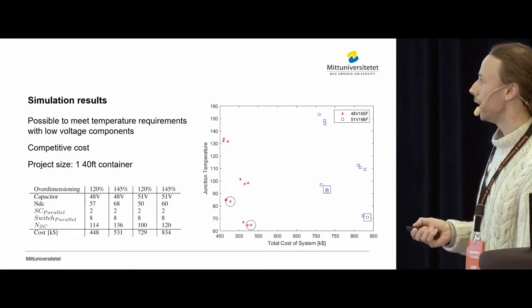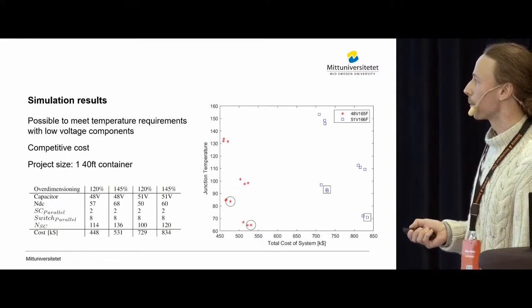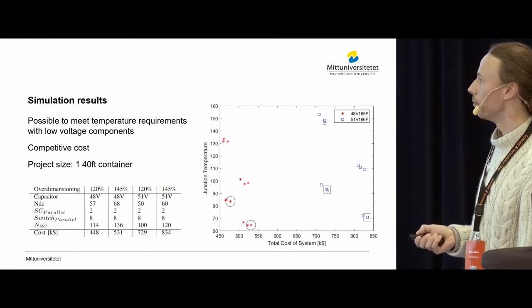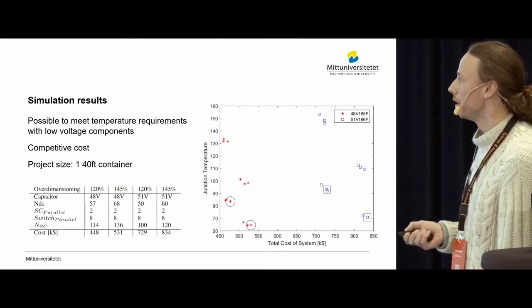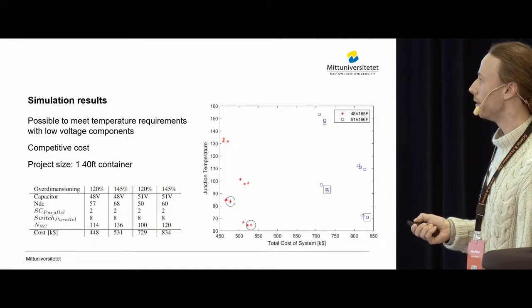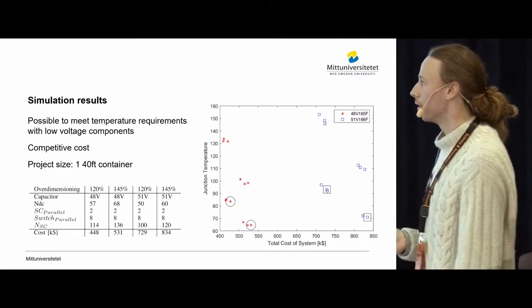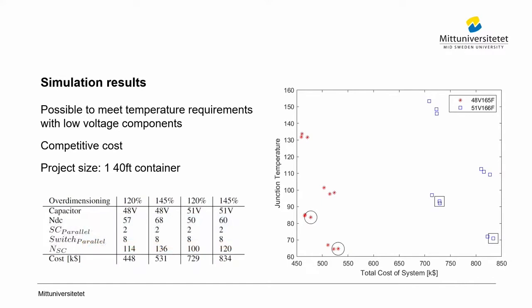I will conclude by saying that all of this is the number of supercapacitor modules needed to supply this energy, and we have between 50 to 68 sub-modules in the multi-level converter. This is a project size that would fit in one 40-foot container, so it's possible to do this quite densely. The cost ranges between a bit above $400,000 to a bit over $800,000, depending on which technologies you choose.